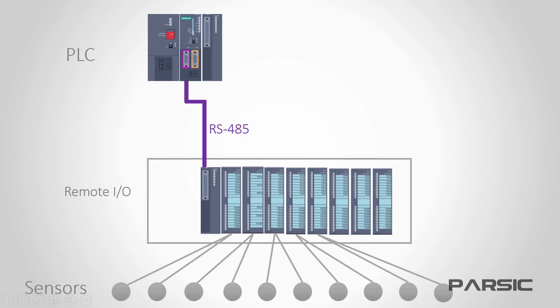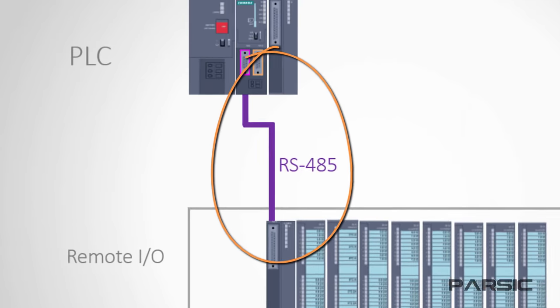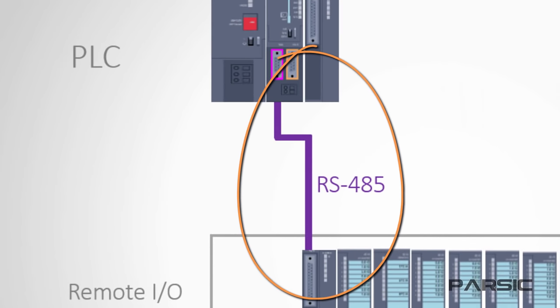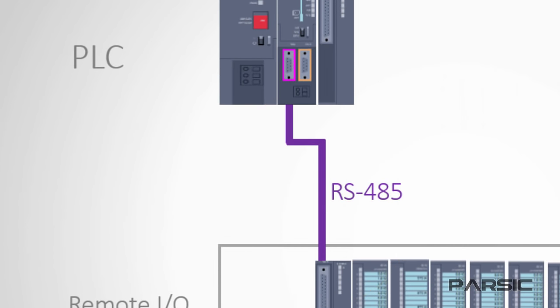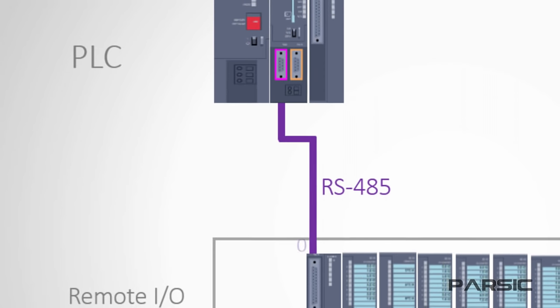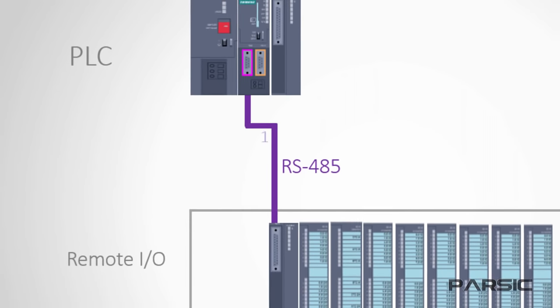So, using Profibus DP, instead of wiring each individual sensor, actuator, or other facility to the PLC individually, we can install a set of remote I.O.s next to these facilities in the field area and then transfer the data to the control area using a single RS-485 cable. This can decrease the cost of wiring dramatically. And on top of that, since the data transmission method here is digital, industrial environment noise has less of an impact on data. So, data communication between the control and field areas will be more robust.